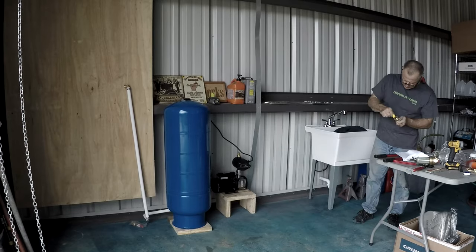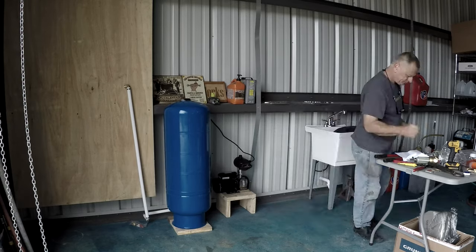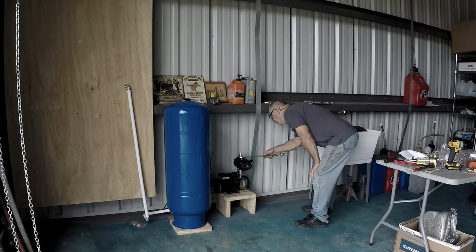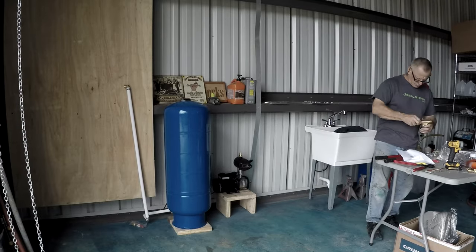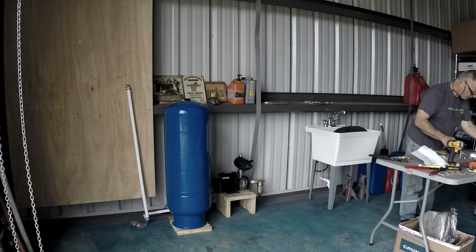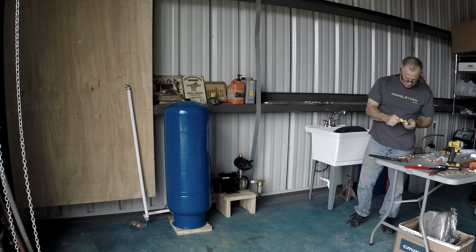Here you see me working on the pump — that's a RainTech HP pump with an actual digital controller. You can preset the pressure you want to come out of it to the house or whatever. The output from the pump is going to go into the tank — it's a pressure tank — and we'll probably run it around 60 PSI, upwards of 60 PSI.